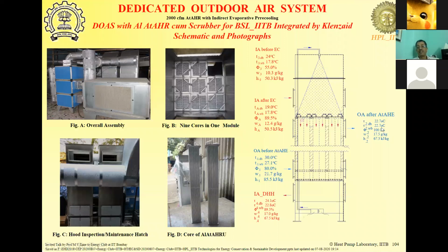This 19-degree air is then used to cool the outdoor air in Mumbai, typically, let's say, at 30 degrees centigrade and 27 degrees wet bulb temperature, so around 80% RH. So this humid air comes in and goes out at 22.7 degrees centigrade with 100% RH. So the temperature has been dropped from 30 degrees to 22.7. And if you notice carefully, even the humidity has been reduced from 21.7 grams per kg to 17.5 grams per kg. And this is all using just the air being exhausted. And in the process, you are also getting it scrubbed.